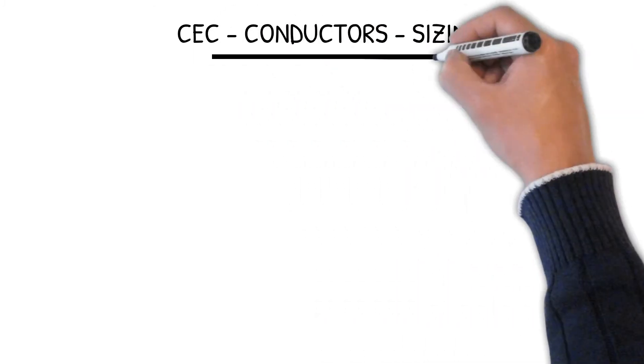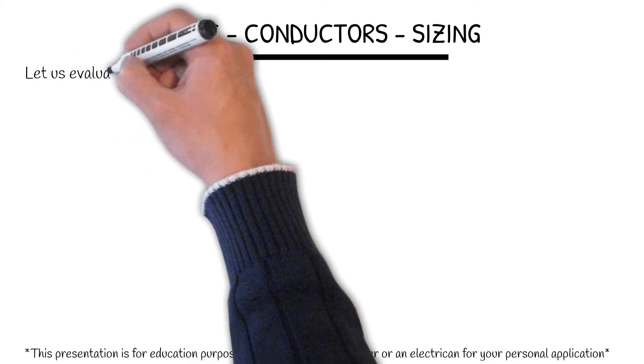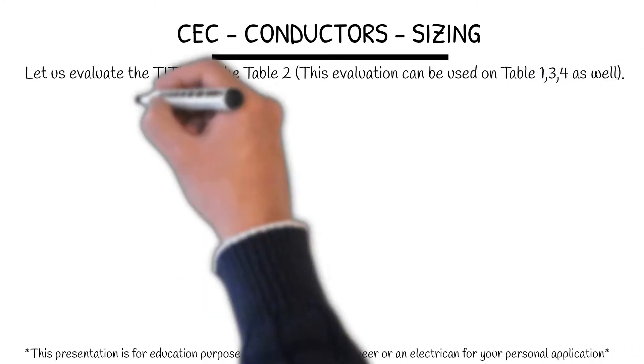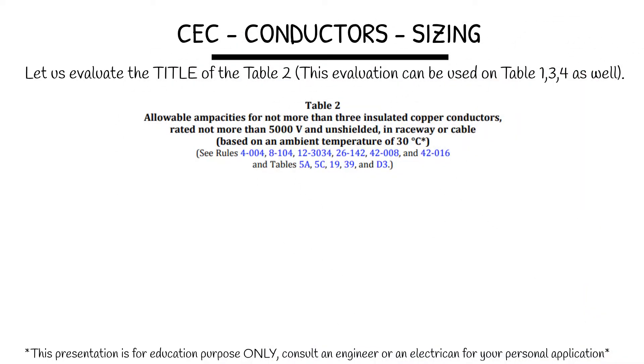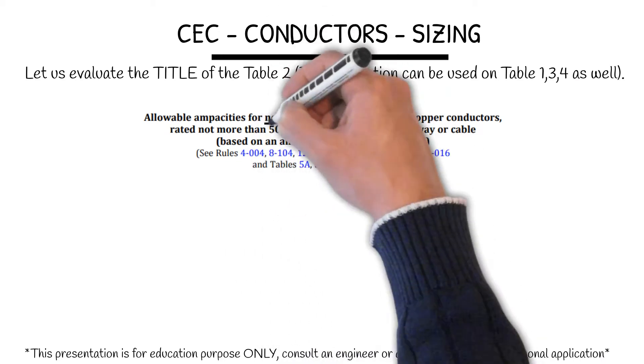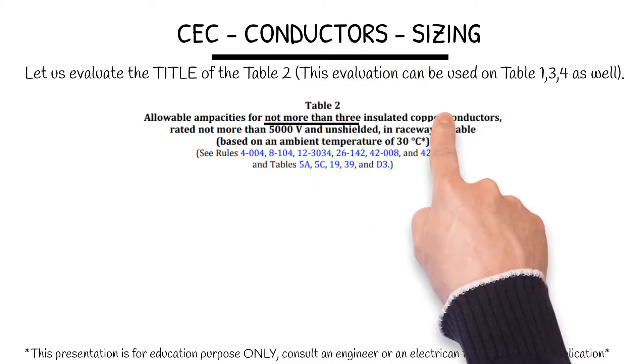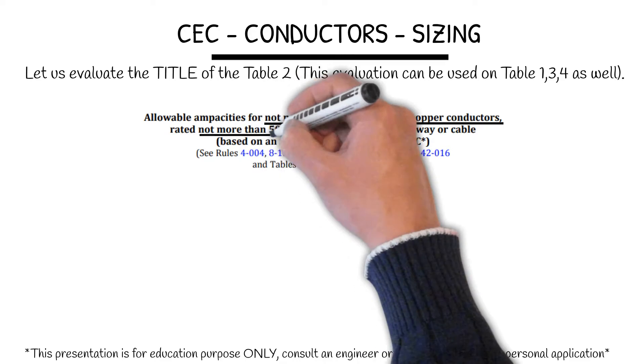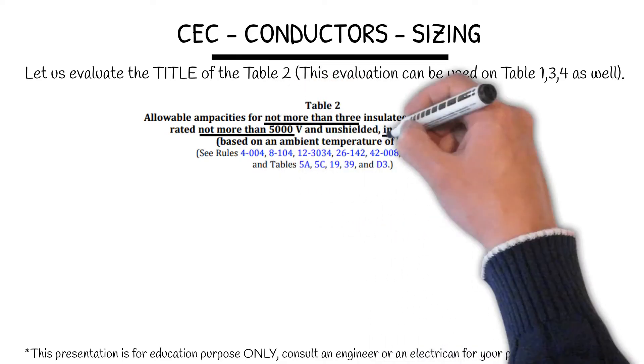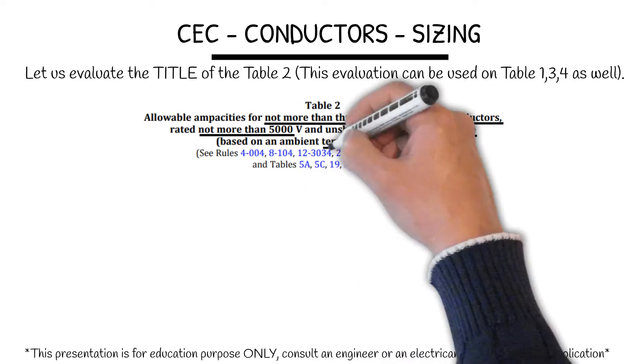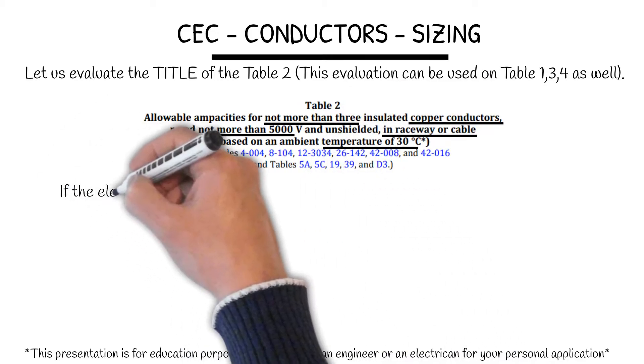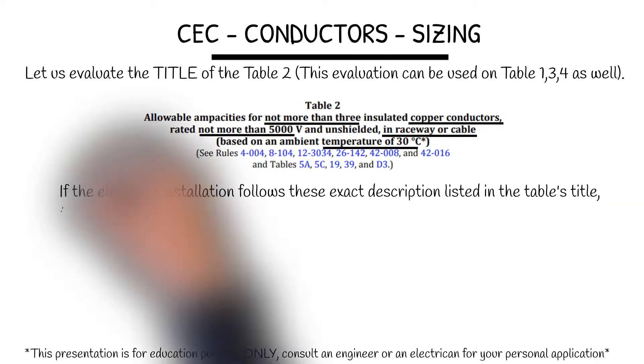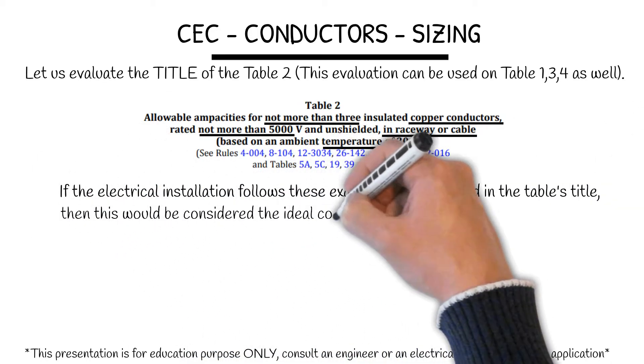CEC Conductor Sizing. Let us evaluate the title of Table 2. This evaluation can be used on Table 1, 3, and 4 as well. Allowable ampacities for not more than 3 insulated conductors, copper, rated not more than 5000 volts, unshielded, and in raceway or cable based on the ambient of 30 degrees Celsius. If the electrical installation follows this exact description listed in the table's title, then this would be considered the ideal condition.